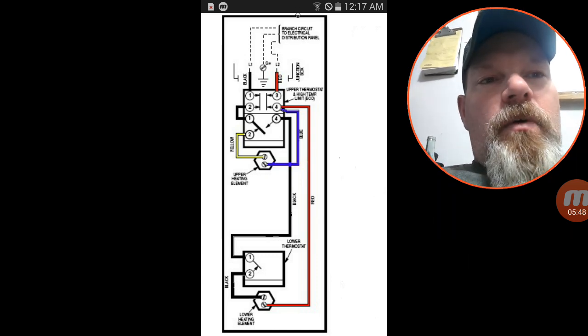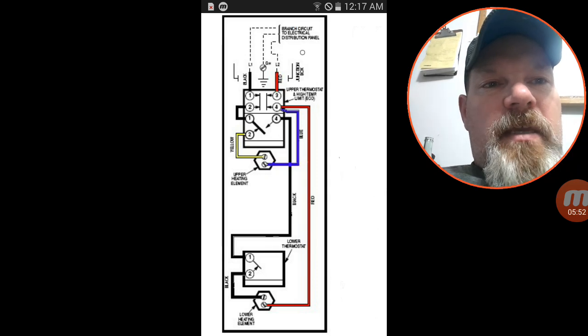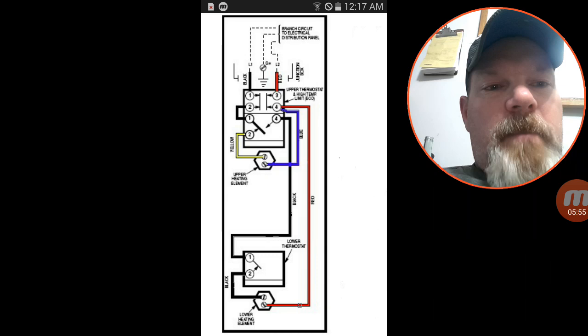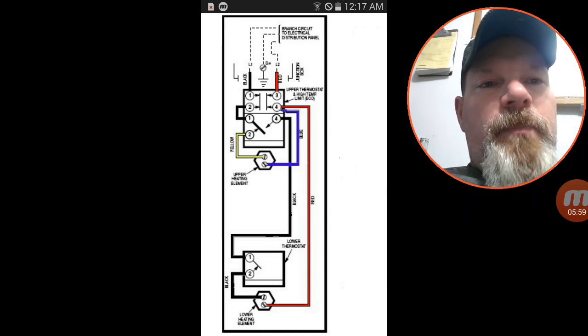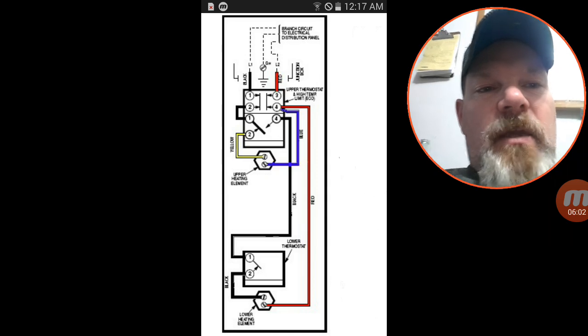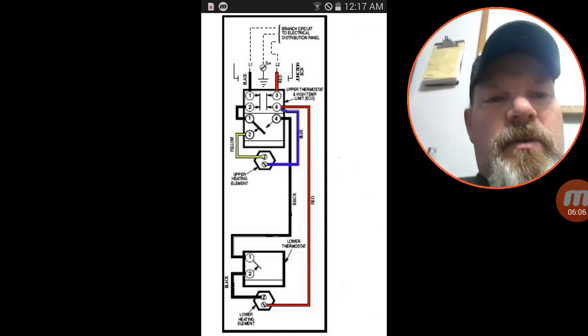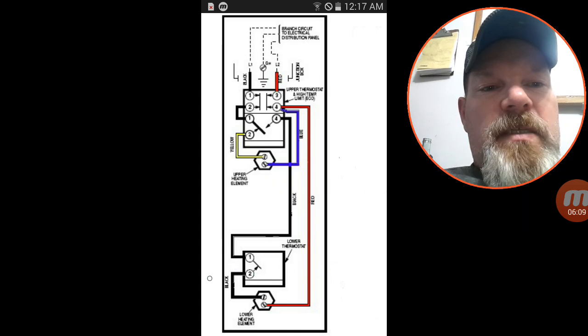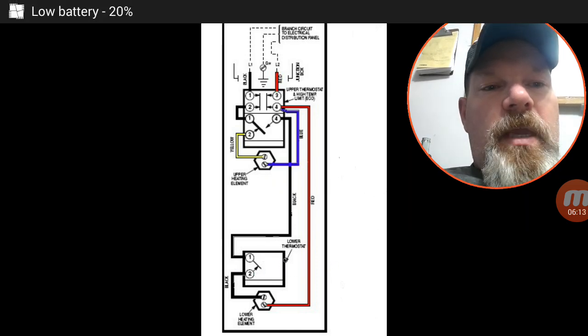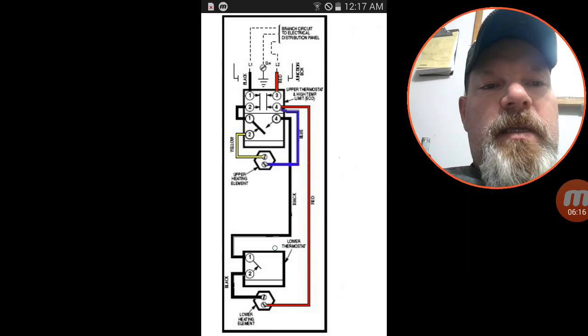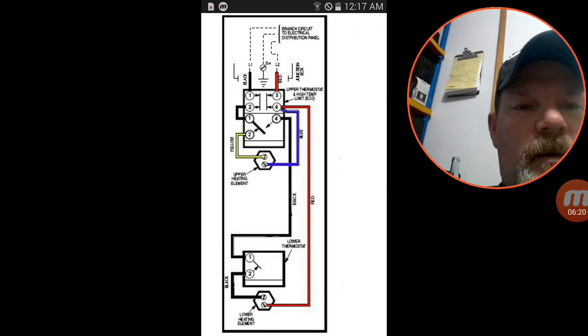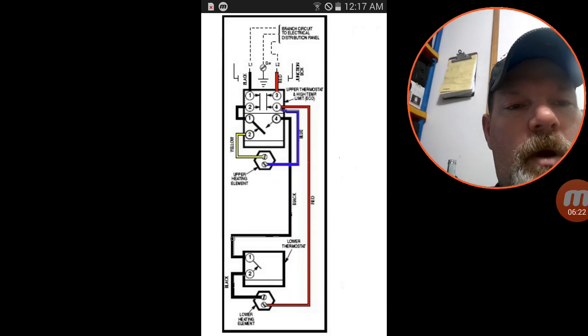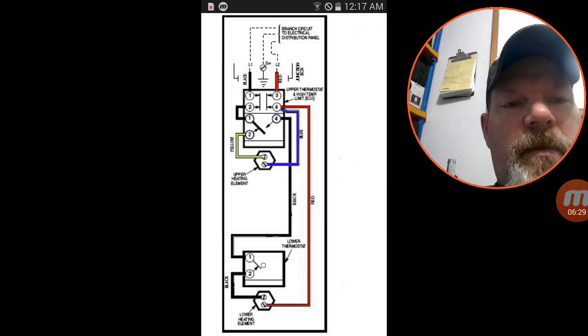The other side is cold. The cold water side has a dip tube that brings the water all the way down to the bottom of the tank. So as you draw hot water off the top of the tank, cold water is entering the bottom of the tank. And you need to understand that stratification happens. Basically, the difference between the cold and the hot water is going to be pretty consistent. So as you draw hot water off the top, more and more is entering the bottom of the tank.